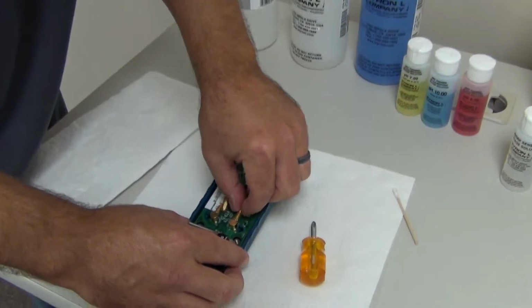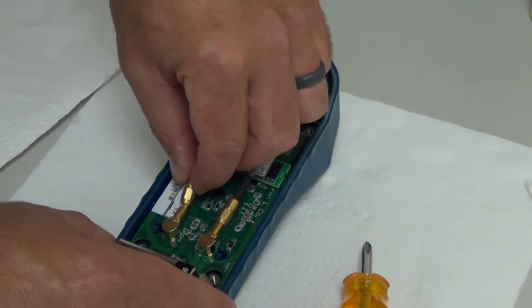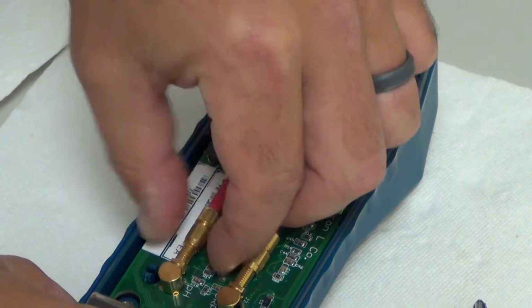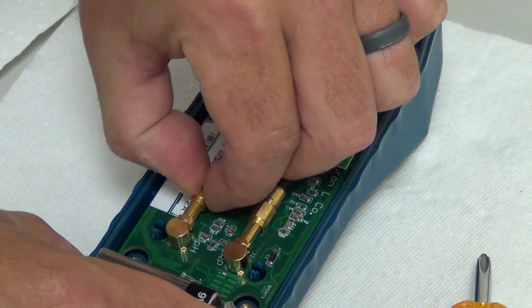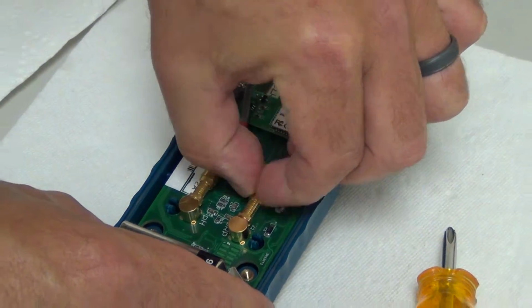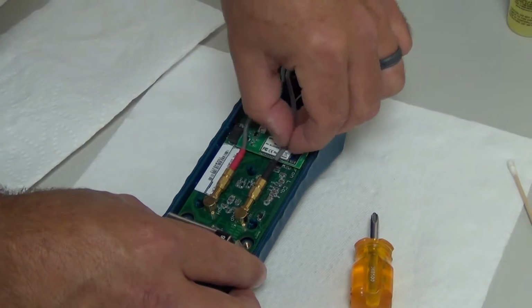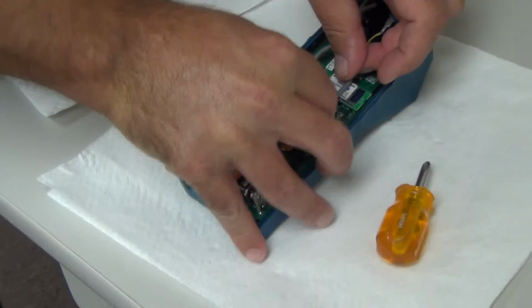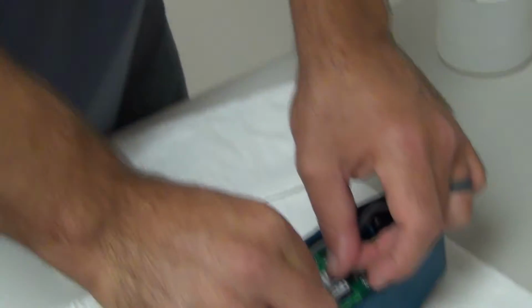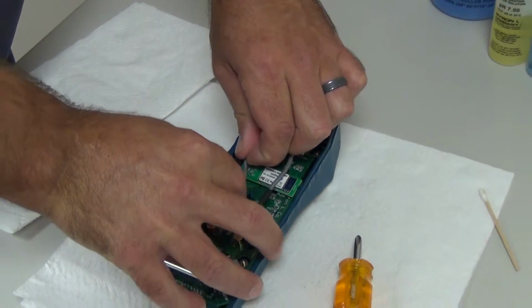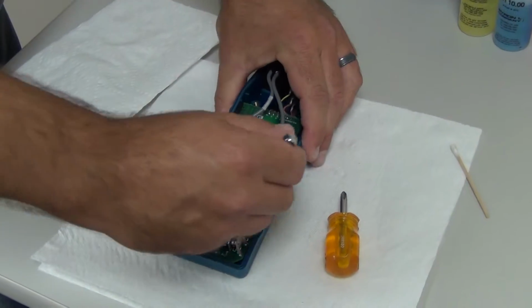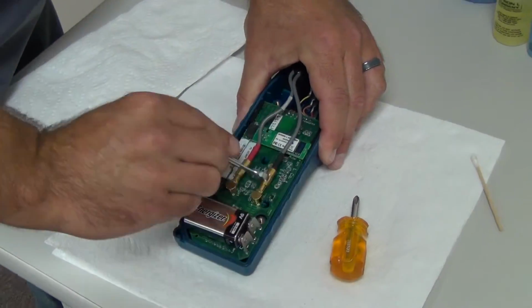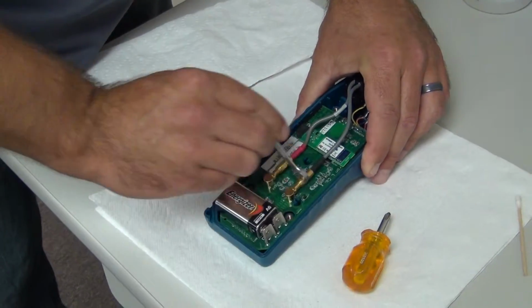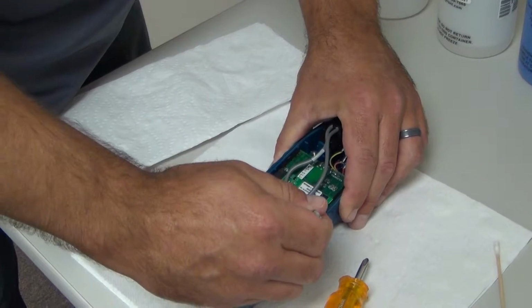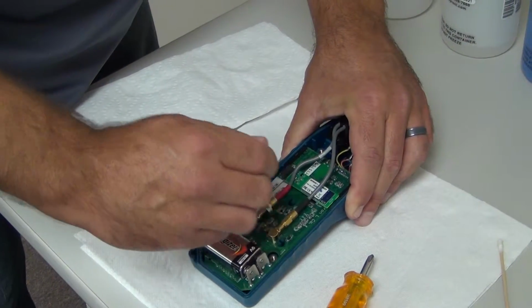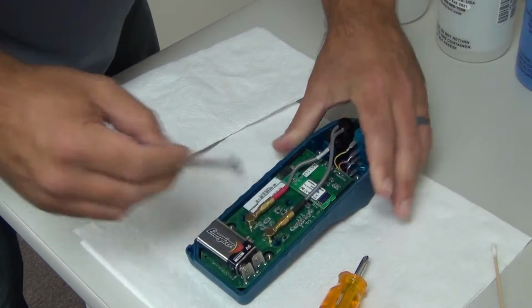Hook my electrode wires back in. Again, as you can see, I'm touching the board as little as possible. Once I have these hand tight, I take my 1/4 inch wrench and just snug them up. That's good and tight, and that's good and tight.